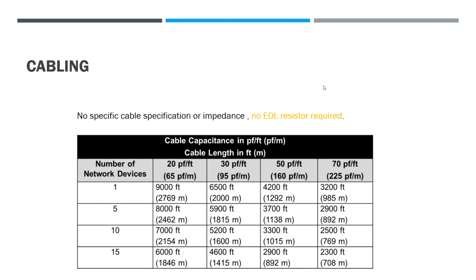How do they measure it? It's comprised of the end device along with all the cabling involved. You may have noticed in the lab, when you tried to hook up a HART device and couldn't communicate with it, we had to throw a resistor into the loop. That's because normally the cable is long enough to have enough ohms per foot that you get 250 ohms just from the cabling. But in the lab our cable runs are very short, so we don't get that resistance, which is why we add the resistor.